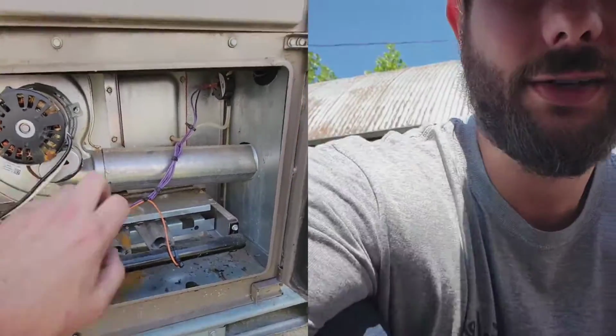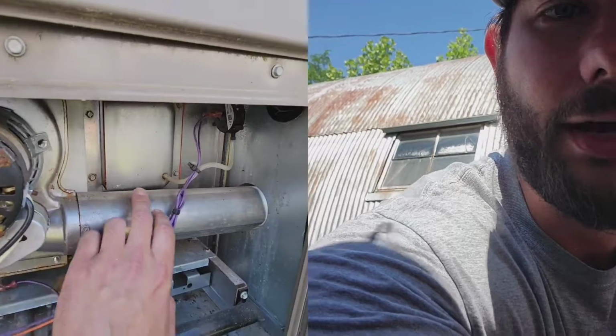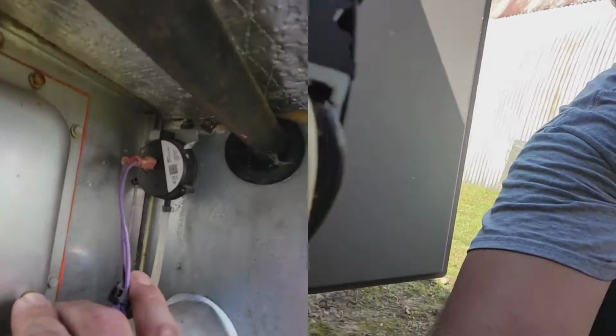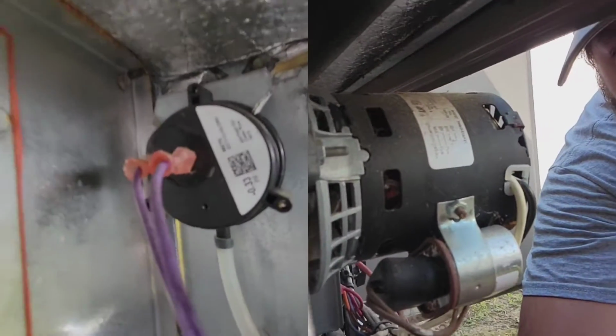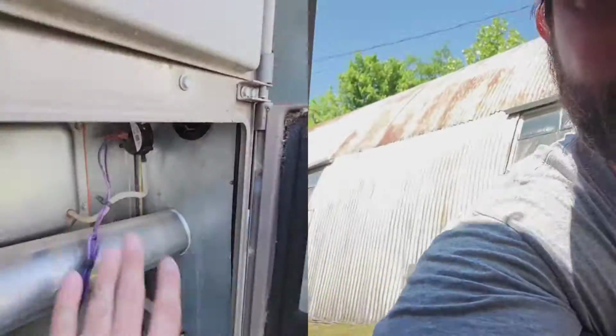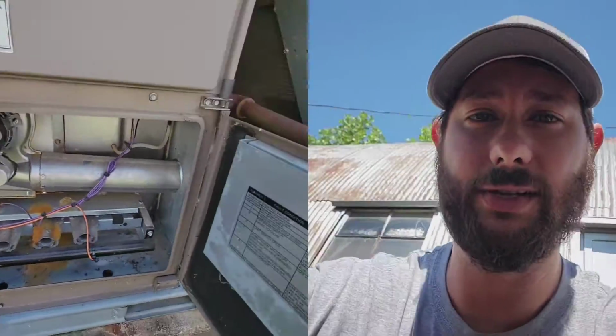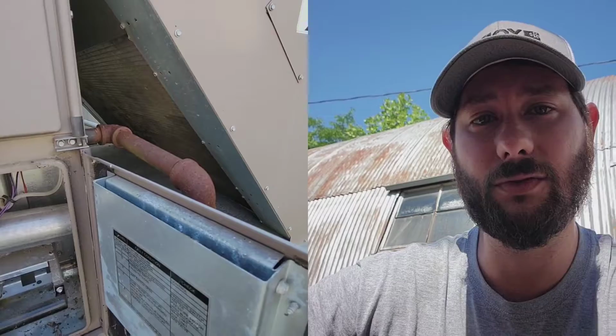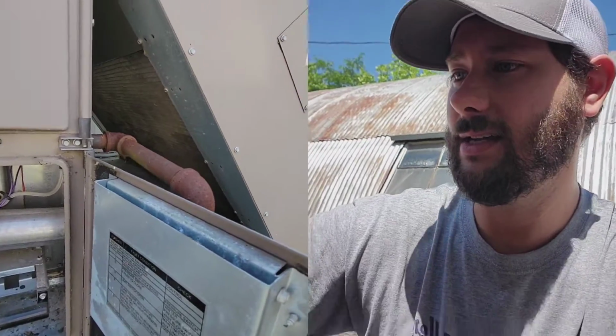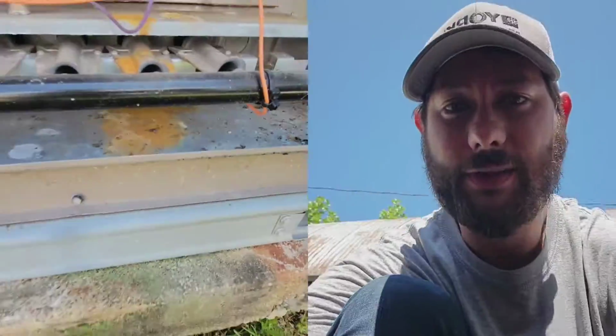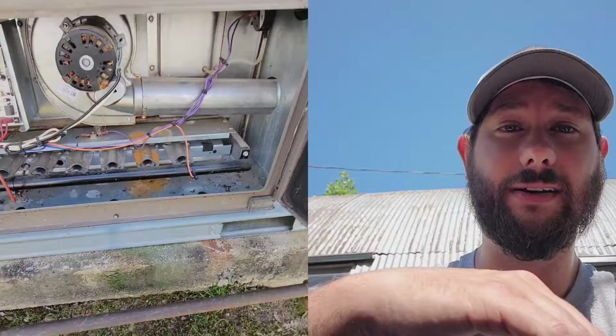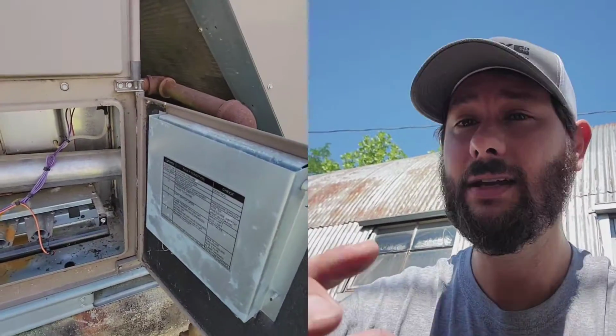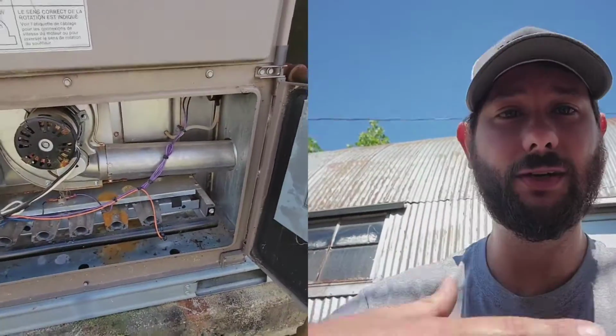Your inducer motor starts, it's gonna pull a pressure, and it's going to be a negative pressure, and that pressure is going to be 0.33 or greater, and that's going to close that pressure switch. And then your cycle is going to keep on moving through your safeties, and then the ignition. This right here is your spark igniter, and you should hear it spark, and that's your flame sensor. Flame sensor could be dirty. That's a very common problem. All you got to do is take it out, get some sandpaper, clean it off, you're good to go.